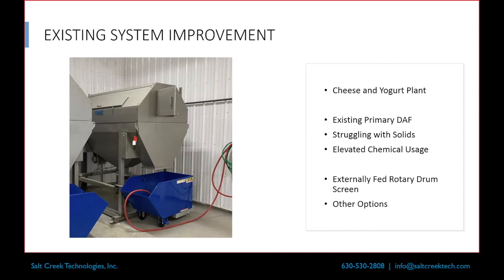They called us in, and while I would have loved to have actually replaced the DAF that was there, that would have been a quick meeting if that would have been my proposal. We ended up just deciding to install an externally fed rotary drum screen to remove the solids before they hit the primary treatment system.